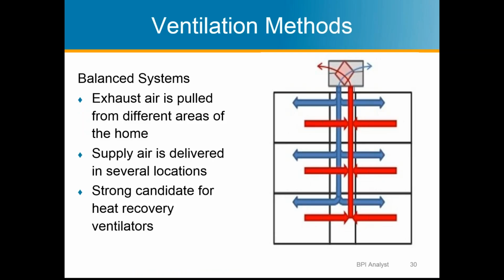Okay, so balanced systems. Balanced systems exhaust the air out of the home, so you could have an exhaust system in the bathrooms and laundry rooms. That's where the dirtiest air is typically found: bathrooms, laundry rooms, and kitchens. So you can exhaust air from those rooms, and at the same time you supply air into the house. The best design is going to have the supply air going into the bedrooms, so you've got people kind of trapped in their bedroom for hopefully 8 hours a day at least. So you're able to supply the freshest air into those rooms while you're exhausting it out of the rooms with the dirtiest air: kitchens, baths, laundry rooms.